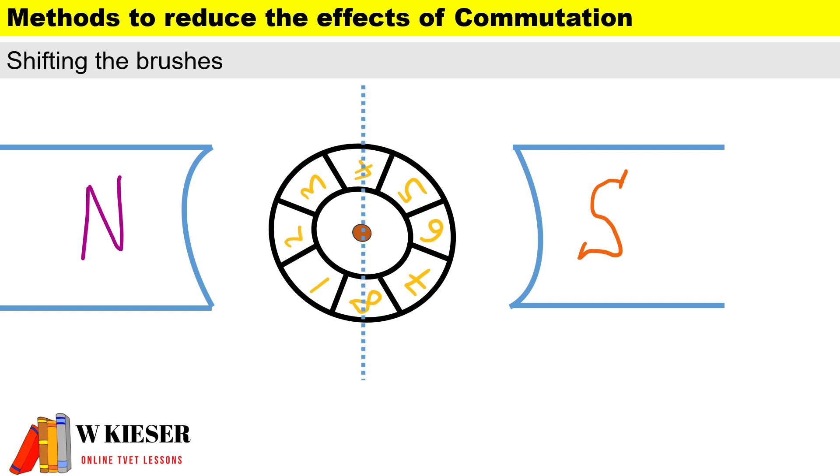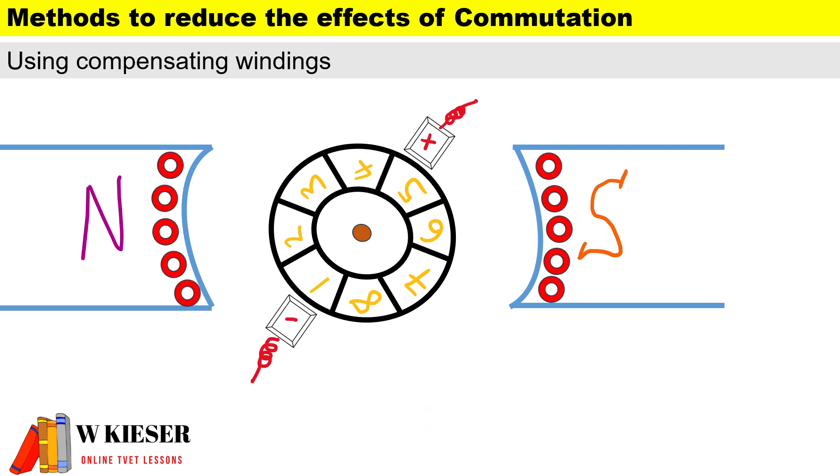We shift the brushes from the geometric neutral axis to the magnetic neutral axis. For motors we shift the brushes backwards, and for generators we shift the brushes forwards. We can also use interpoles, which are smaller poles found in between the main poles.